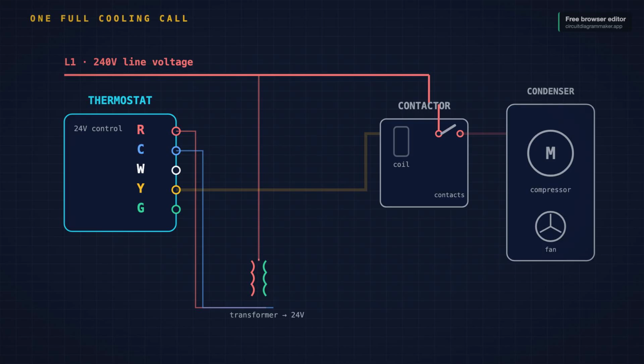Let's trace one full cooling call, start to finish. You set the thermostat to cool. The room warms up past your set point. Inside the thermostat, a switch closes, it connects R to Y. Now that 24-volt power is on the Y wire. Y runs outside to the condenser unit and lands on the contactor.